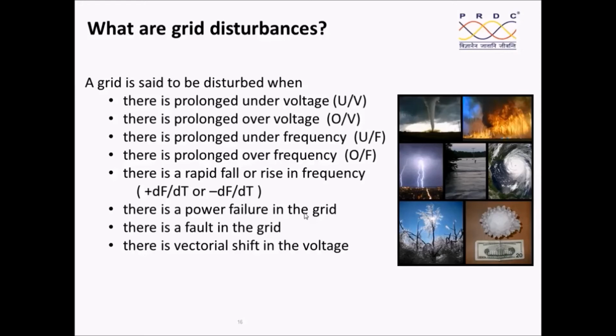There is a vectorial shift in the voltage. What do we mean by this vectorial shift? Assume that we are either importing or exporting power and we have synchronized with the grid. As soon as the grid is lost, there can be a sudden voltage shift. That is what we call a vectorial shift in the voltage.